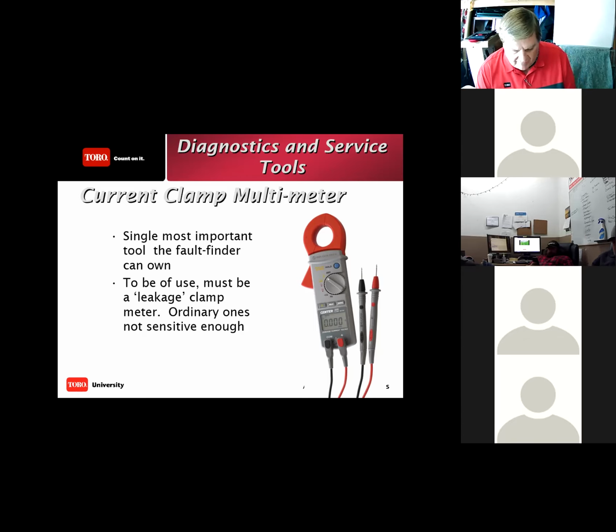You must have this device here. It is not an inexpensive device. It can range from $250 to $400, depending upon what one you get. Underhill sells one. Armada sells one. Fluke makes one. Many different brands. X-Tech out there. There's a lot of different brands out there. It just has to be a leakage current device. That's the walk away. That's what you must know. It must be a leakage current device, able to read small milliamps going out into the system.